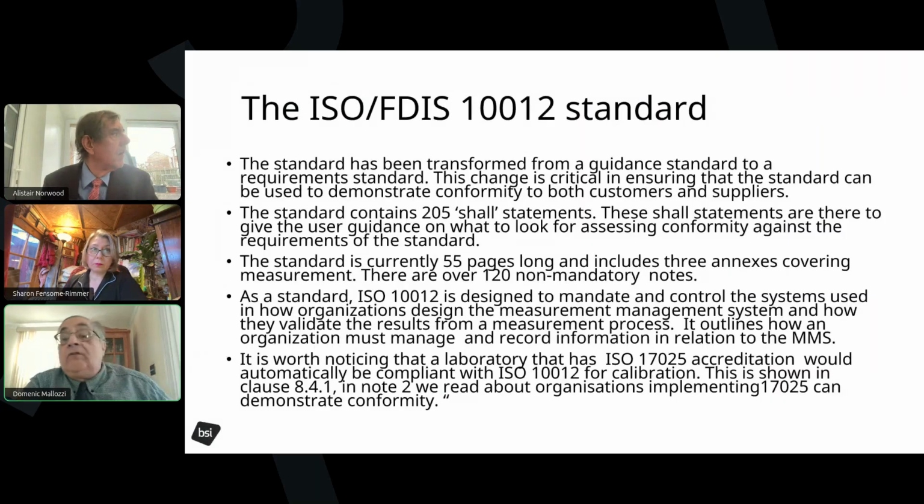What this means is if you have a cal lab or a test lab providing you services and they meet 17025, they're accredited to 17025, the data we're asking for in 10012 is no more than they're providing. We're not asking you to add to the calibration laboratory task.